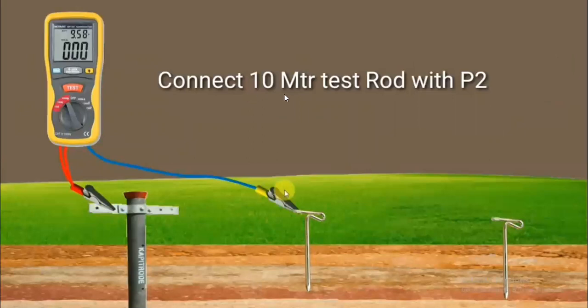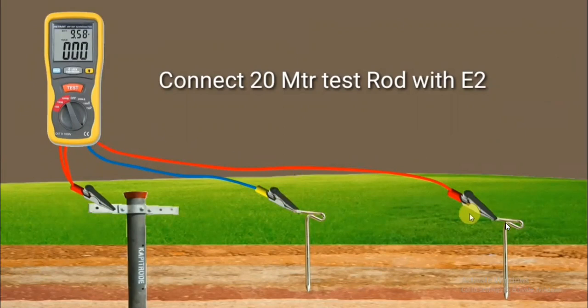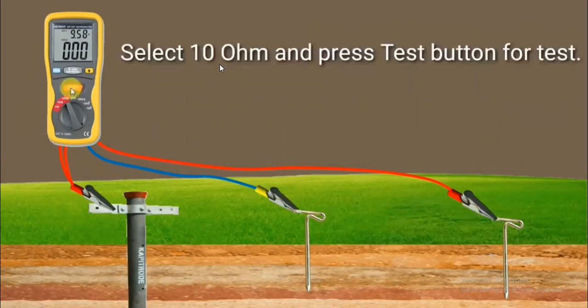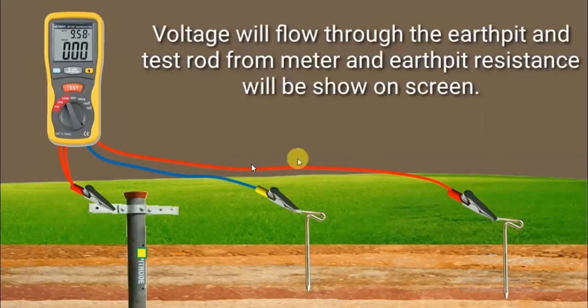Then next, connect the 10 meter test rod to the P2 terminal. Then connect the 20 meter test rod to the E2 terminal. Next, select the 10 ohm range and press the test button. That means we are measuring the resistance value for the 11 kV pole mounted substation, which is why we select the 10 ohm range and then press the test button. After pressing the test button, the potential or voltage will flow through the earth pit.